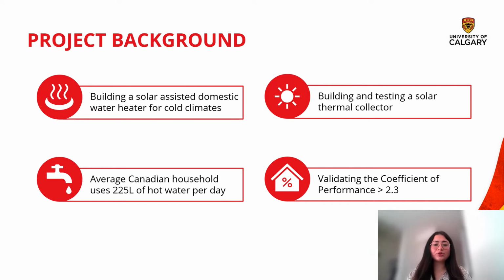Our research focus was designing a direct expansion solar-assisted heat pump that could satisfy the domestic hot water heat load demand of the average Canadian household. We placed a lot of emphasis on designing the technology for cold climates because research on the feasibility and operability of these systems in cold weather conditions is somewhat lean, for obvious or fair reasons. Deploying new technologies in climates of high precipitation and low bright sunshine hours is challenging from both a technical and financial standpoint.